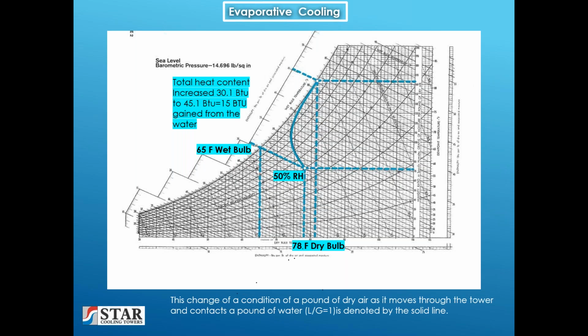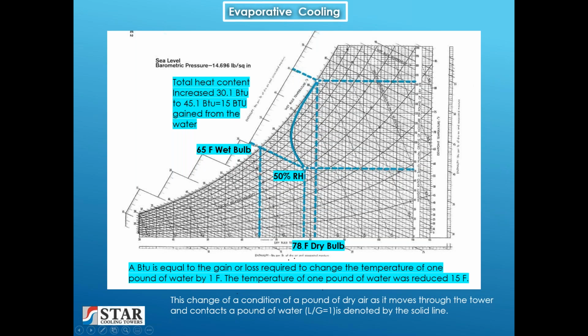This change of condition of a pound of dry air as it moves through the tower and contacts a pound of water, we have a liquid to gas ratio of 1, denoted by this solid line. A BTU is equal to the gain or loss required to change the temperature of 1 pound of water by 1 degree Fahrenheit. The temperature of 1 pound of water was reduced 15 degrees Fahrenheit.